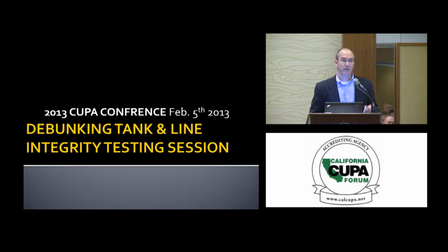We monitor very closely this decay in vacuum that occurs if there is a hole in a tank. And then if there's a hole in a tank that's buried in the water table that draws in water, that water will accumulate at the bottom of the tank. And again, the integral water sensor will measure the increase of water.